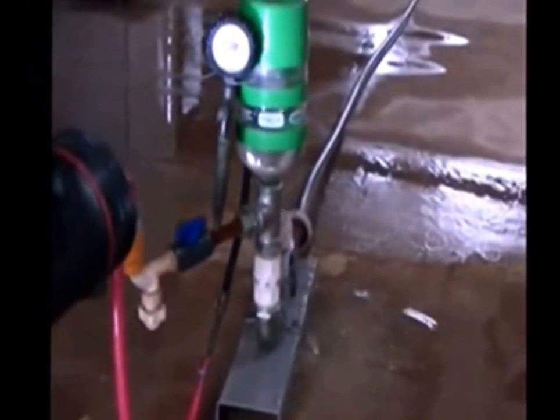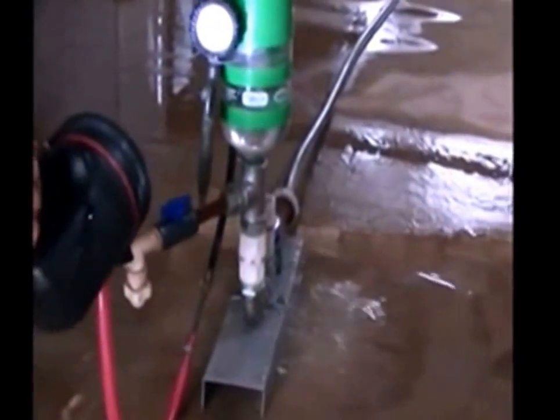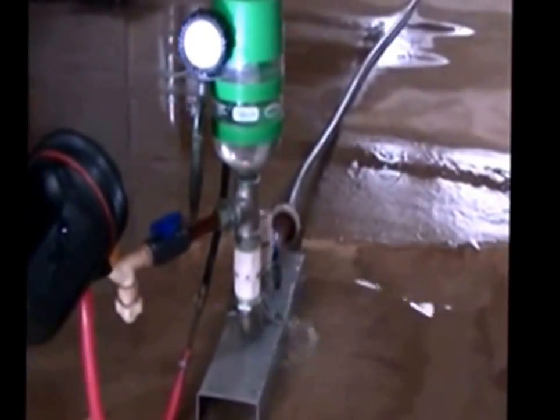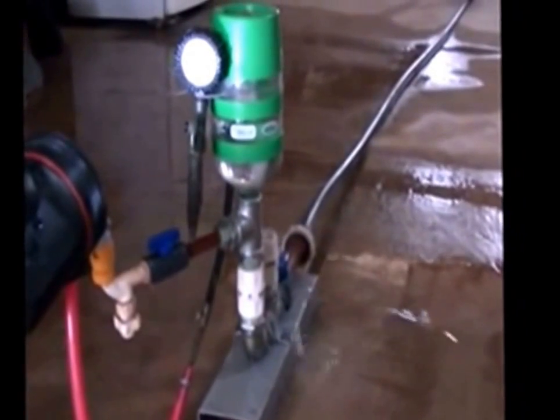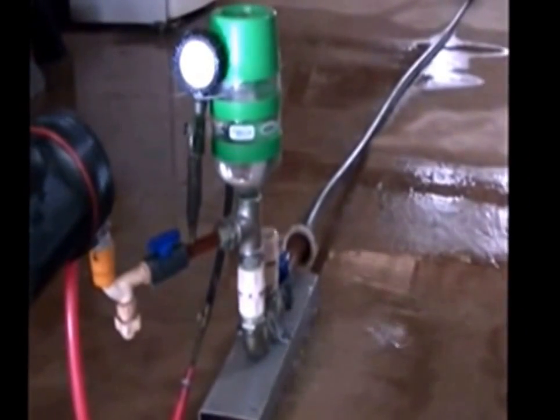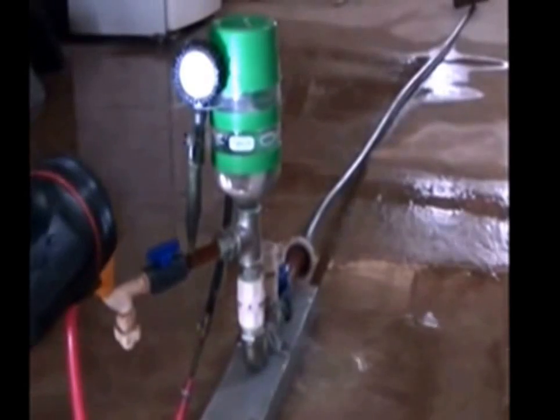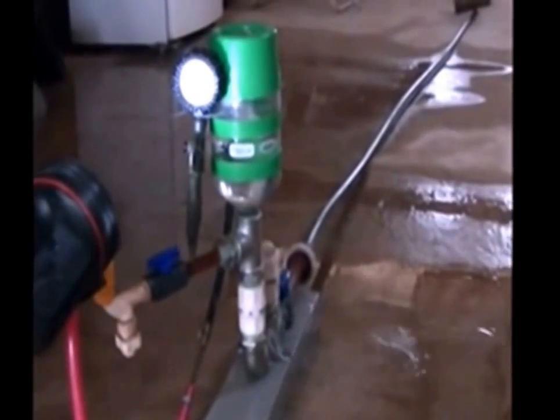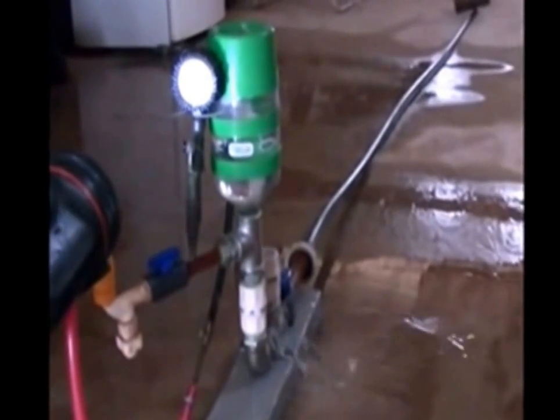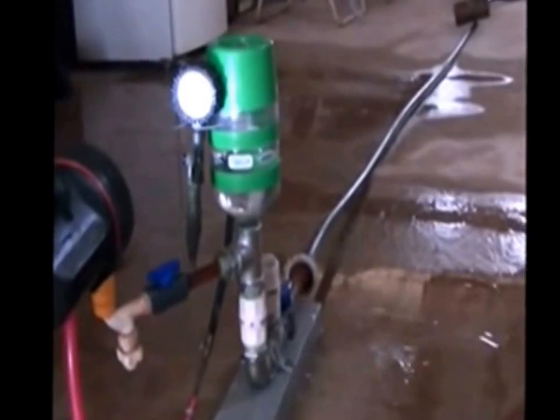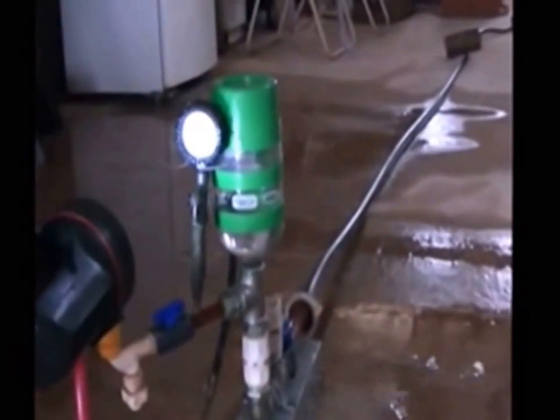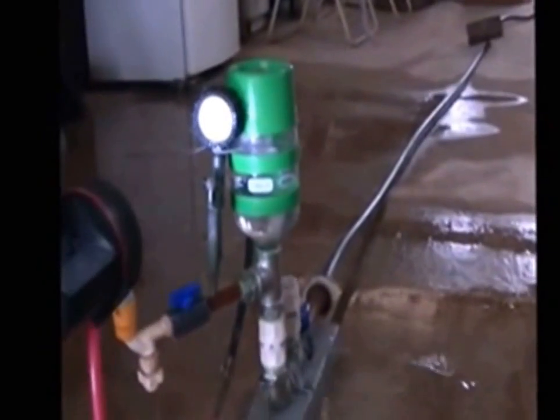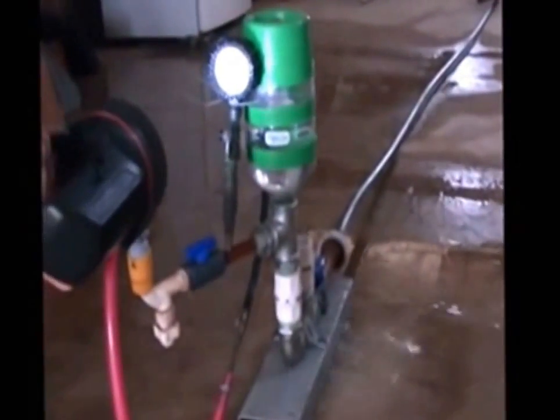There the manometer starts to rise. Now it's about to reach one kilo. There you see one kilo. That means it can already lift 10 meters in height. We wait a moment to continue observing the pressure. 14 meters in height.